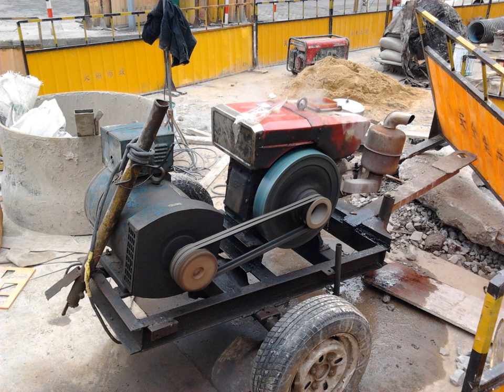Exhausting extremely hot flue gases from gen sets can be done by factory-built positive pressure chimneys certified to UL-103 test standard or General Utility Schedule 40 black iron pipe. It is recommended to use insulation to reduce pipe skin temperature and reduce excessive heat gain into the mechanical room. There are also excessive pressure relief valves available to relieve the pressure from potential backfires and to maintain the integrity of the exhaust pipe.